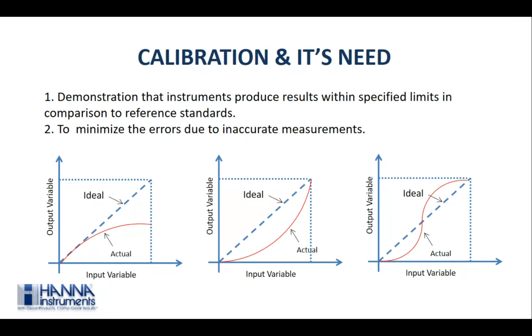Then how could one understand, after all these precautionary practices, whether the pH electrode is working fine and is in good condition or not? The answer for this is calibration. Calibration is a demonstration that an instrument produces results within specified limits when compared to known standards. Specifically, calibration is performed to compensate for the changes in potential within the measuring and reference electrodes as well as the change in potential between them. pH probes are not perfect, therefore they must be calibrated.